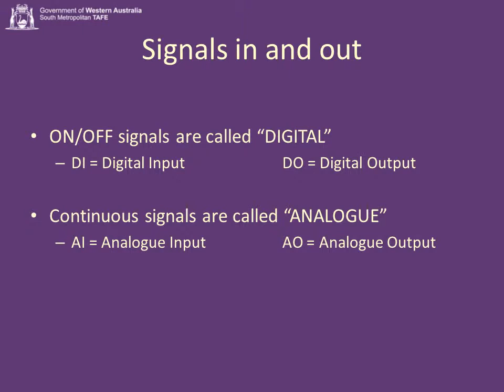This is summarizing that - these are the DIs, the DOs, AIs and AOs. Collectively, we call these things points. And we compare control systems by comparing the number of points they have, so that I might say this building's got 10,000 points, that building's got 5,000 points. Or in a specification it'll say the control system needs to have 10,000 points with 20% redundancy.